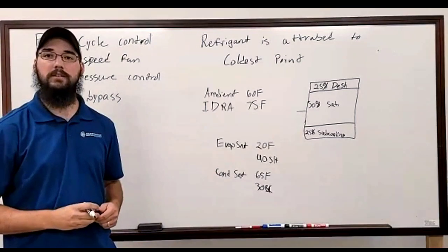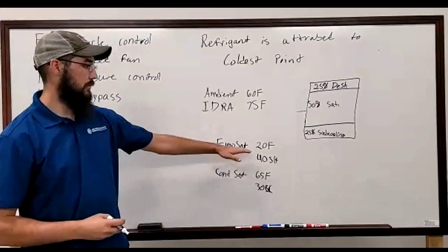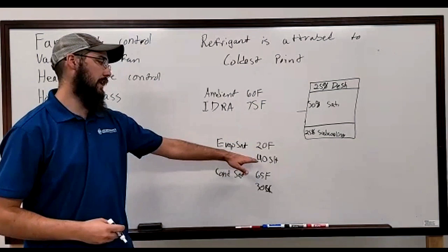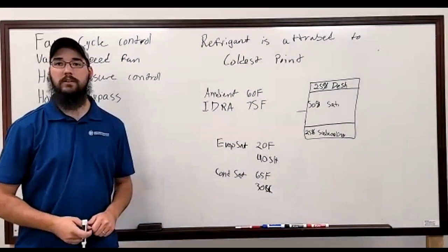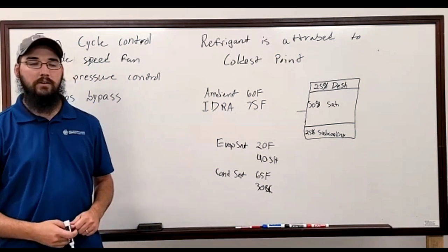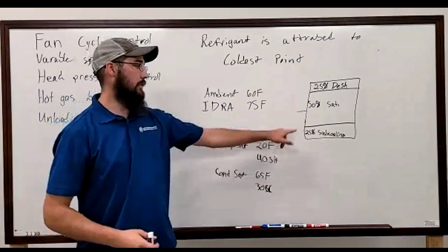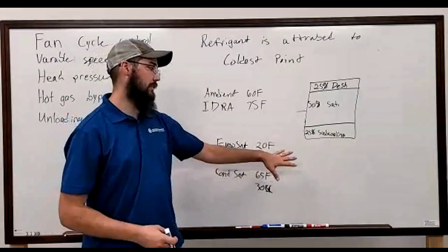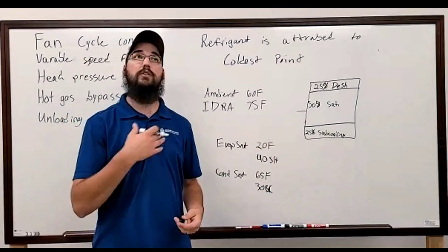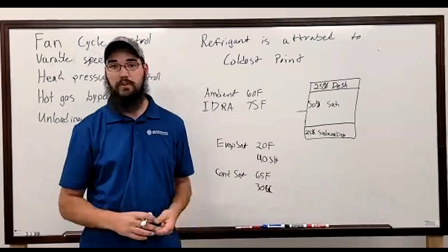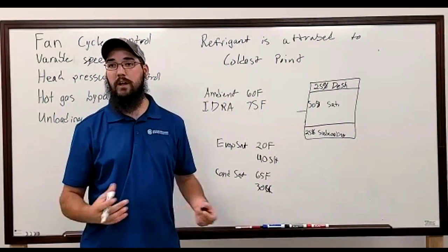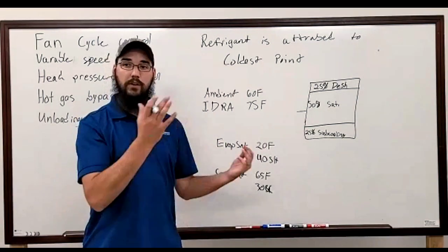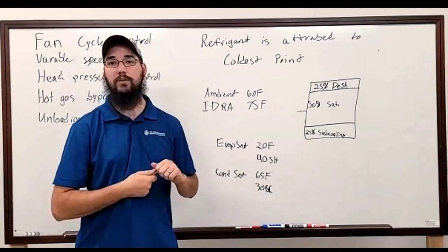Quite literally, you might see 30 degrees of subcool, a 65 condenser set, a 20 degree evaporator set, a 40 degree superheat. Right. This is strictly because it's all staying right here. It's not actually flowing, and you're seeing it represented in the temperatures and all. Your discharge superheat on the compressor is going to be pretty significant. The compressor is going to be running hot during this time frame. Your evap coil will freeze up. You're going to see all the classic symptoms, and a lot of people misdiagnose these with low charge.